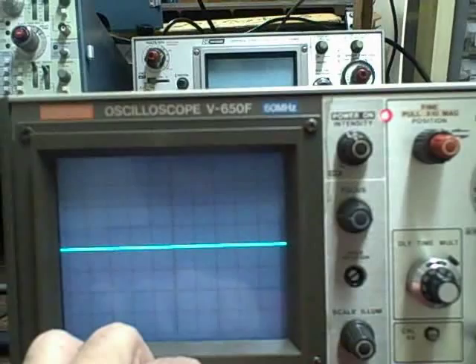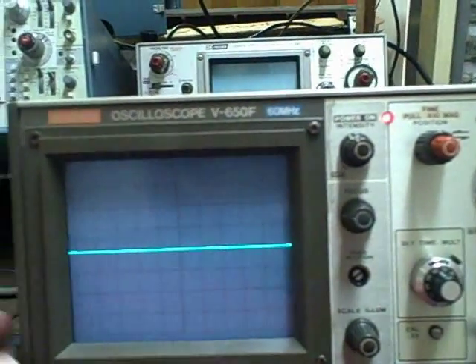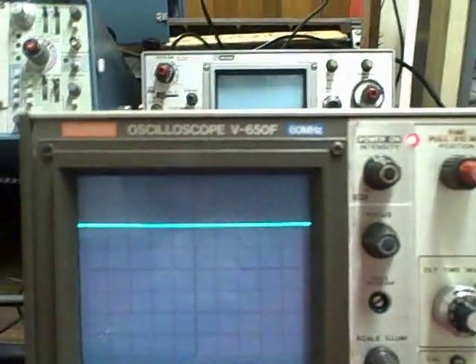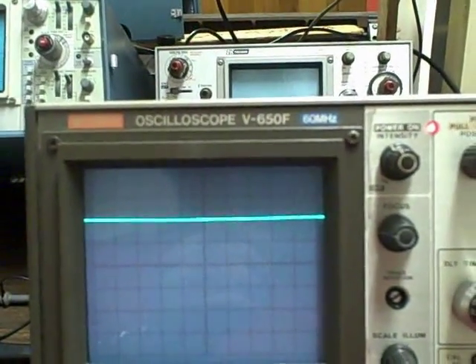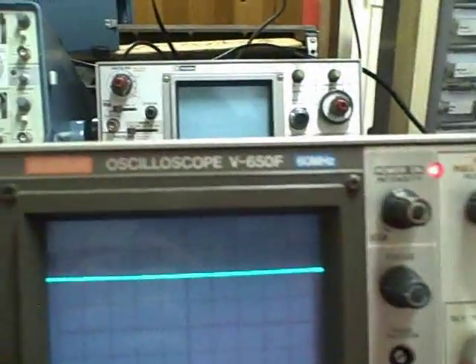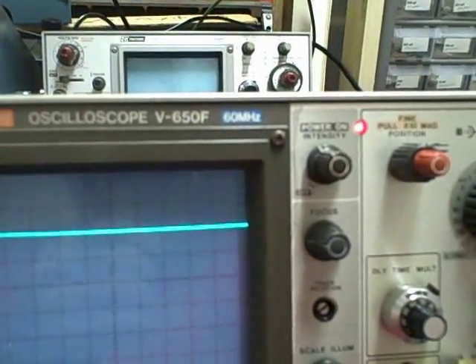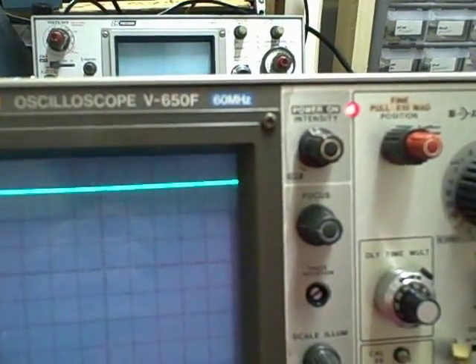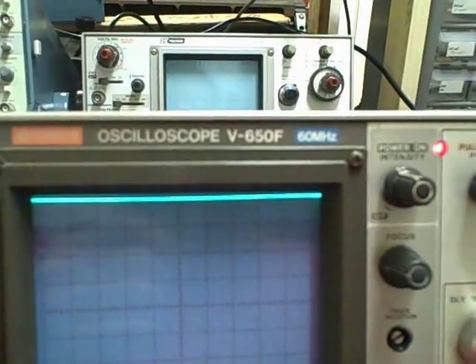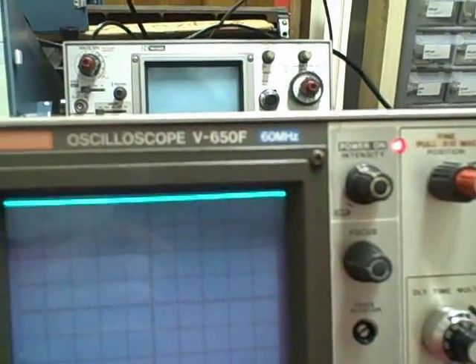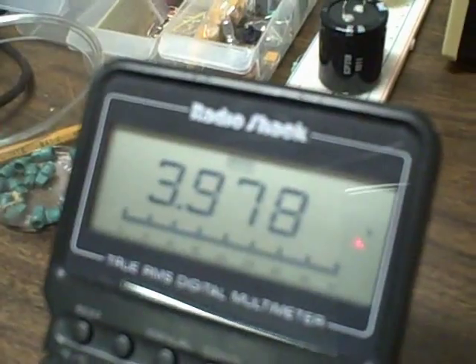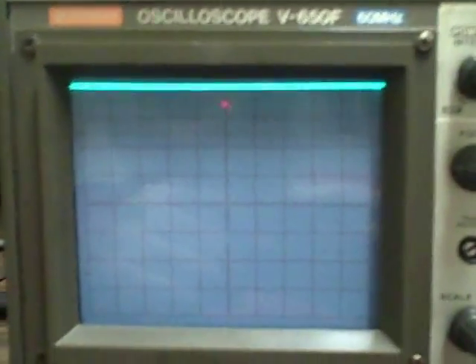Check zero. There's two divisions at one volt per division. That's two volts. We'd expect that, because we're still at two volts. Let's go ahead and bring ourselves up to full scale. I would say that's full scale. And we are reading 3.978, so 3.98 volts. Within two hundredths of a volt of being four volts, which at one volt per division is four volts. So we're right there.